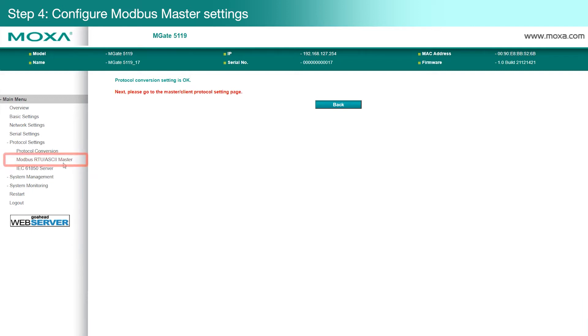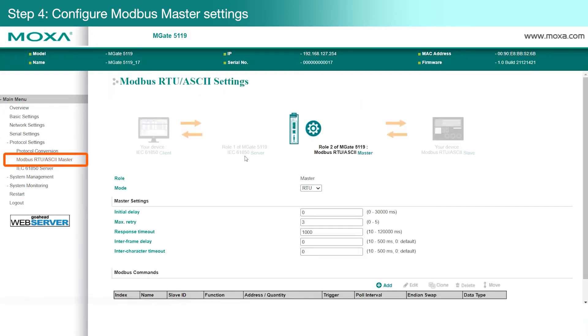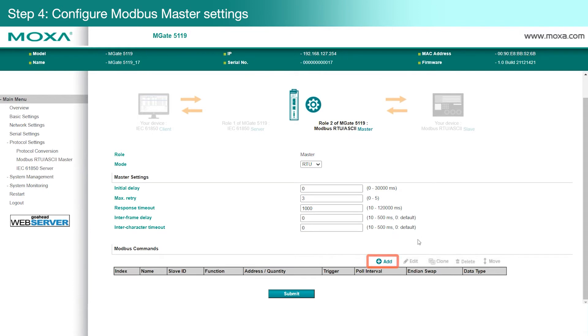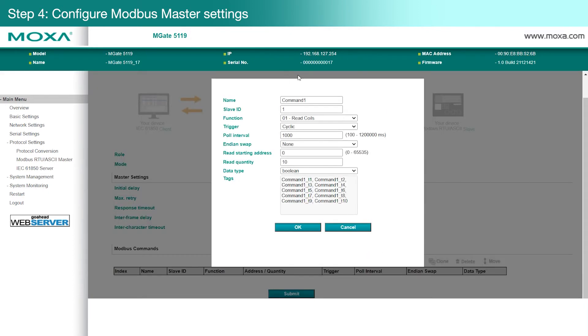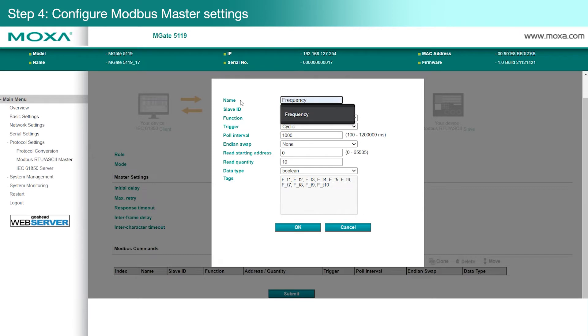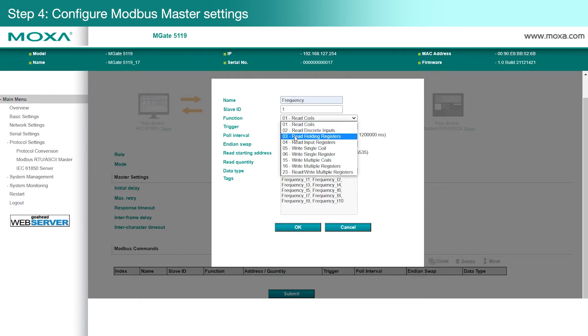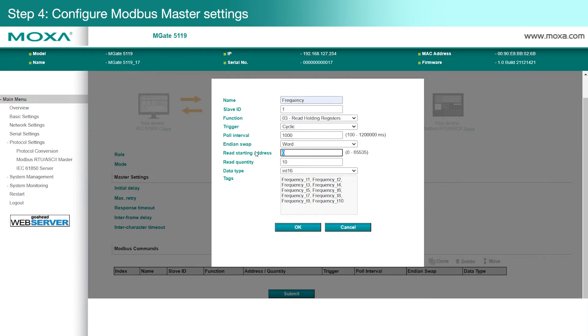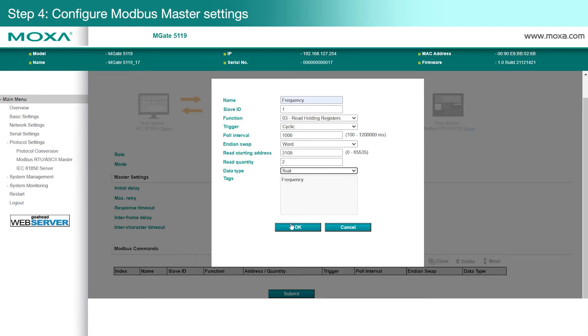On the Modbus RTU ASCII Master page, go to the Modbus commands section and click Add. Enter the details of the Modbus command you want the gateway to handle. We want to monitor the power frequency, so we're going to enter the Modbus command settings for that, then we'll click OK.